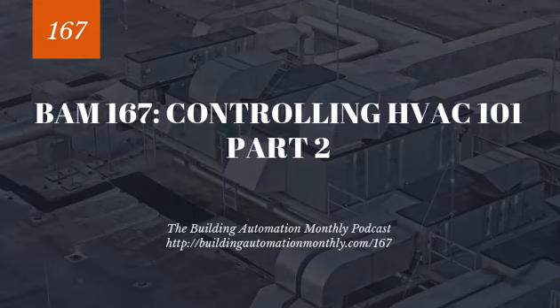I like to have it on a duct run where I get a good intermixing of those box types, because sometimes you'll have reheat boxes that'll be open more than cooling only boxes, and you don't want to be starving a branch of ductwork. So then constant volume, these are just running constant volume.